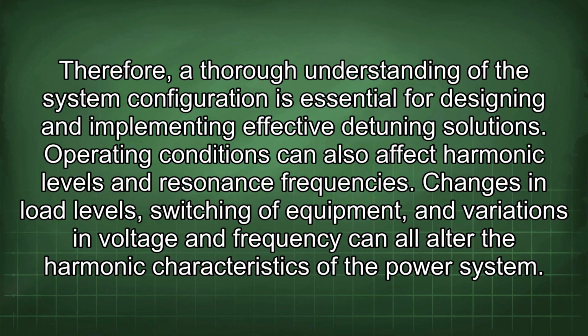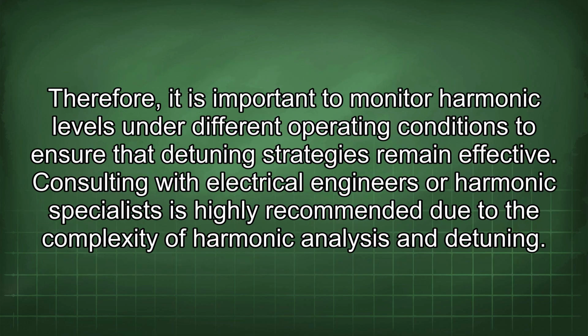Therefore, a thorough understanding of the system configuration is essential for designing and implementing effective detuning solutions. Operating conditions can also affect harmonic levels and resonance frequencies. Changes in load levels, switching of equipment, and variations in voltage and frequency can all alter the harmonic characteristics of the power system.